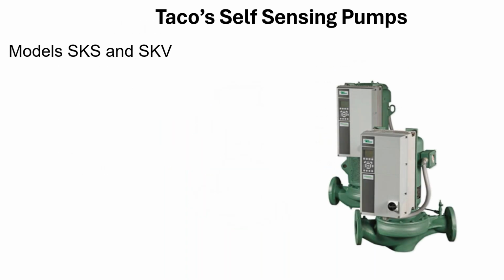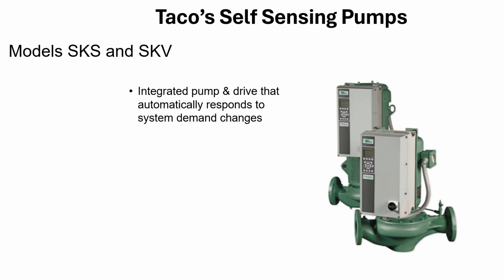it, okay? And there's a picture, two pictures, right? The one in the front is the SKV, the one in the back is the SKS with the drive mounted right to it. And let's talk about some of the details about the drive. So it's an integrated pump and drive that automatically responds to system demand changes. In our world of HVAC hydronic pumps, closed loop systems, right?